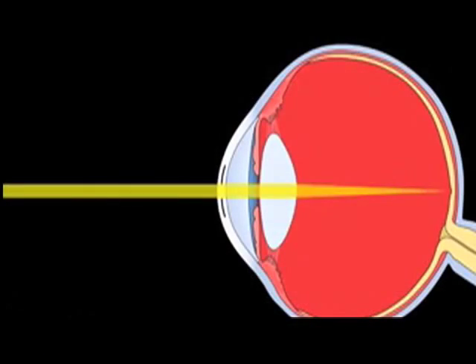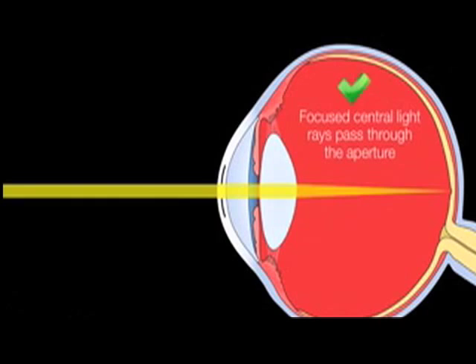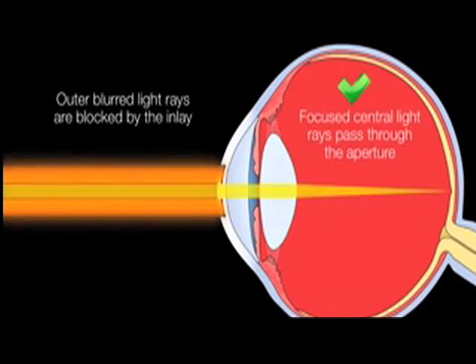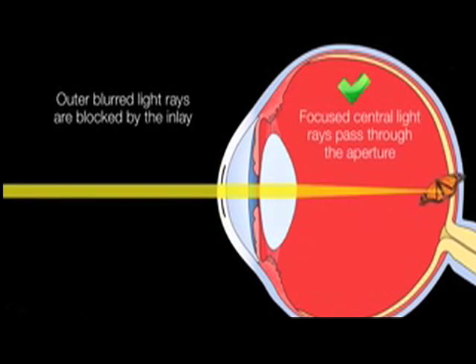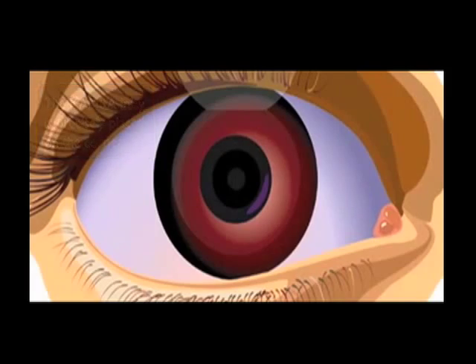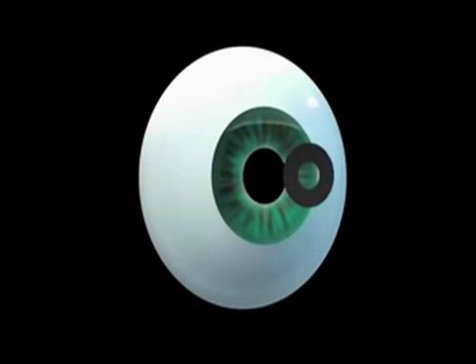The KAMRA inlay functions under the same principle as the small aperture of a camera. It basically blocks all the unfocused light and allows only the focused light to enter the aperture of the inlay, and that gives us the increased depth of focus, which allows us to see at distance and at near.